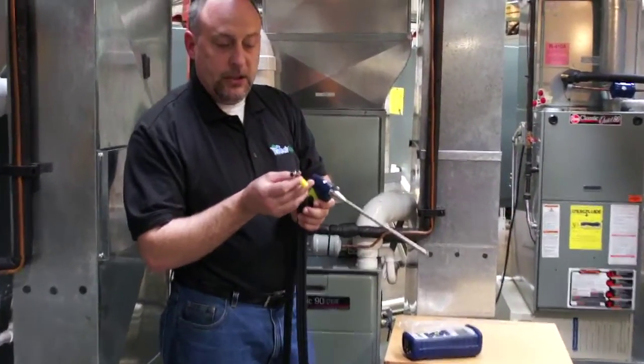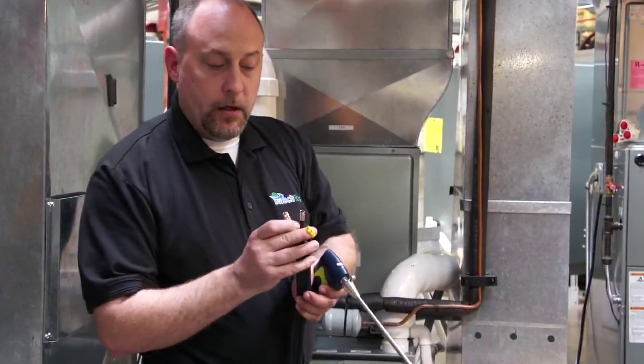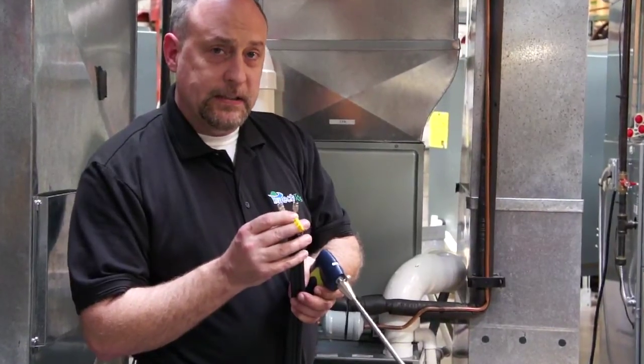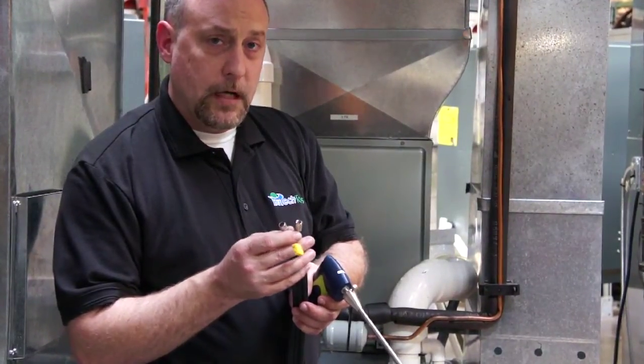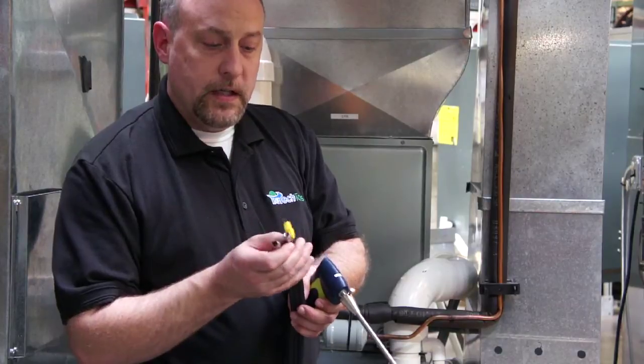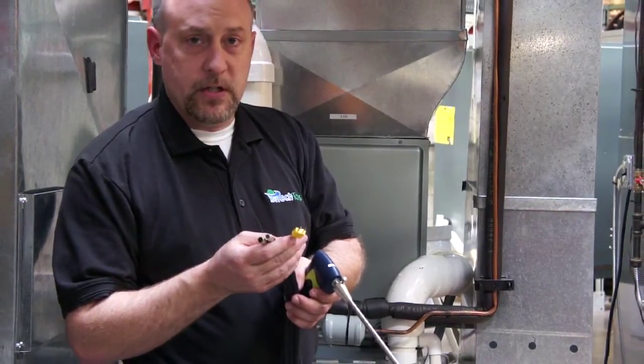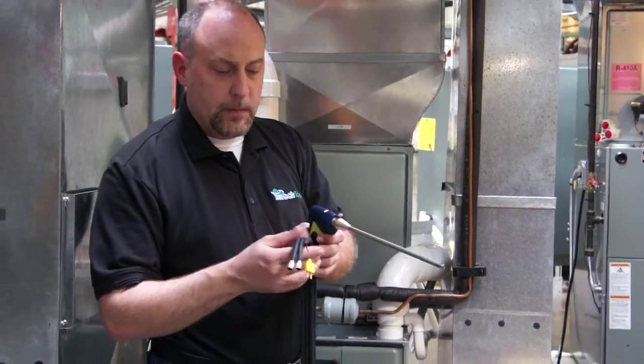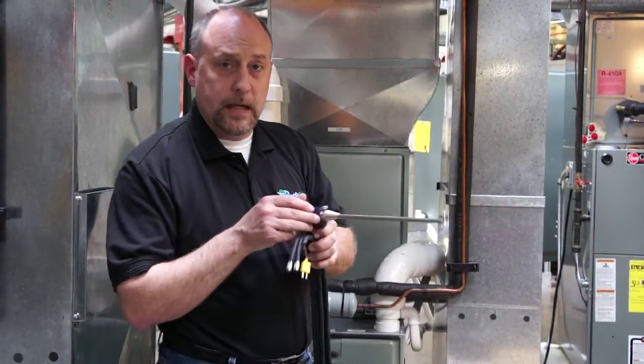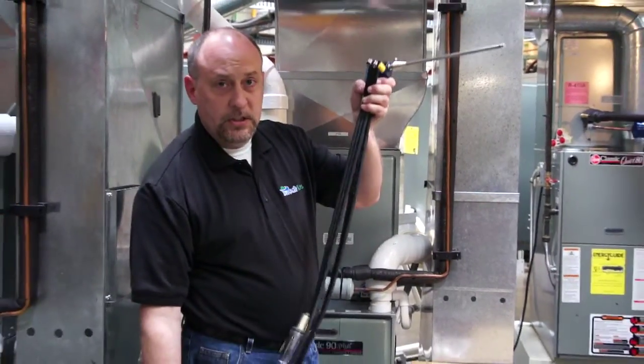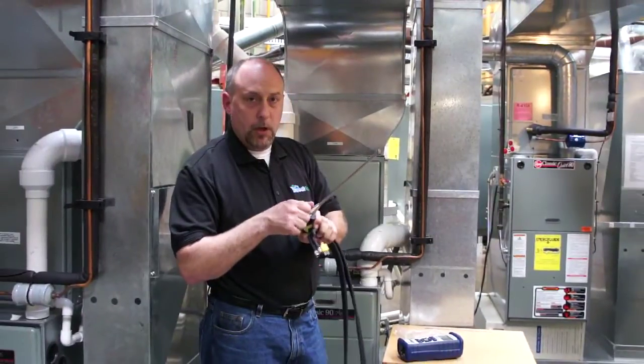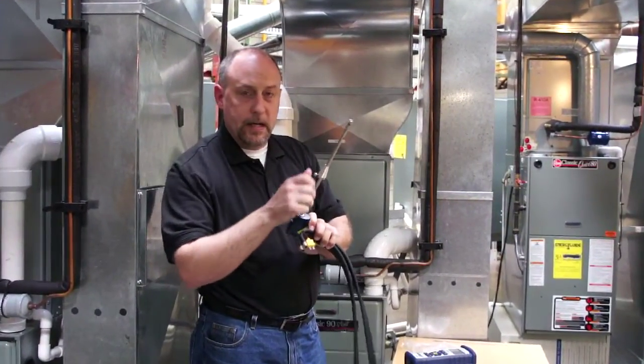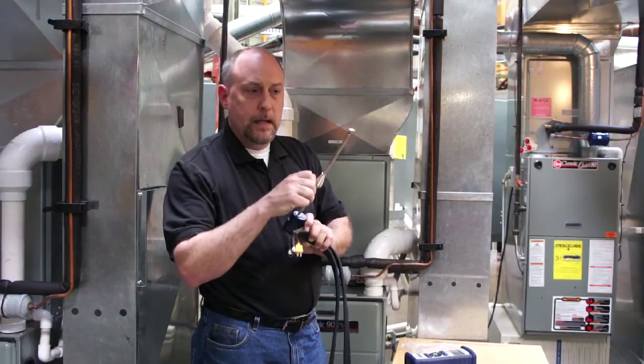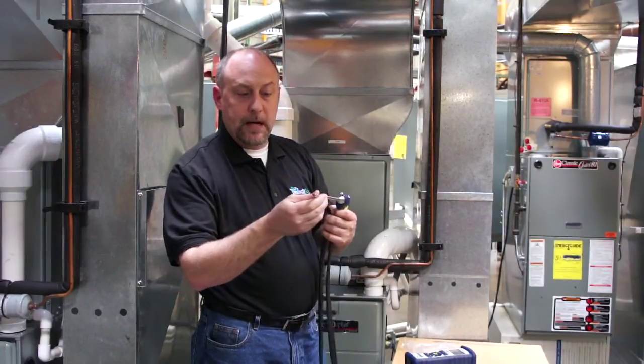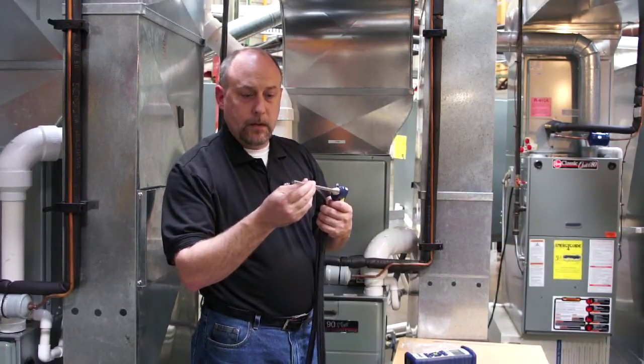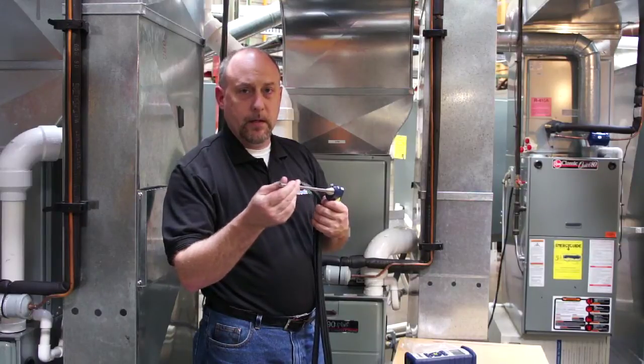When you look at the connections on here, even though they look very close to the same, they are actually sized differently so that you don't get your draft hookup and your flue gas hookup confused. And then we have our K-type thermocouple here for a stack connection. So it's pretty much a simple integrated probe Bacharach's used for a long time with just a little bit longer hose assembly on there. And then we got our adjustable probe stop here so we can set it up inside the flue, get it centered in the flue pipe. And it looks like about a 1/4 inch probe shaft here, to figure out what the hole size is if you need to drill your hole for the stack.